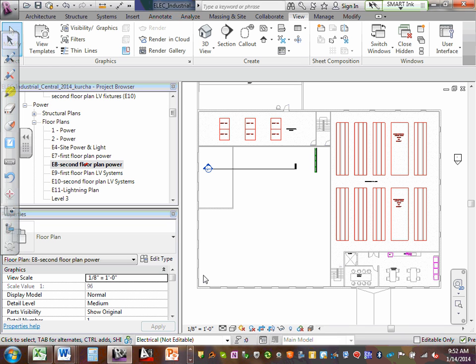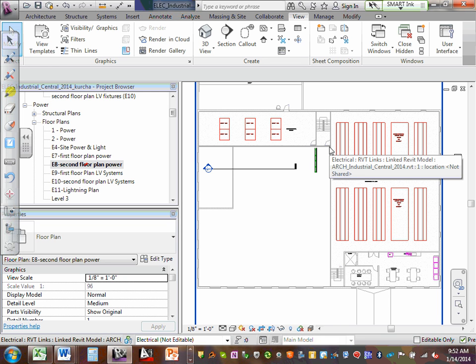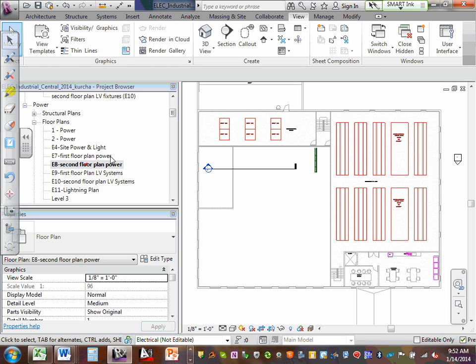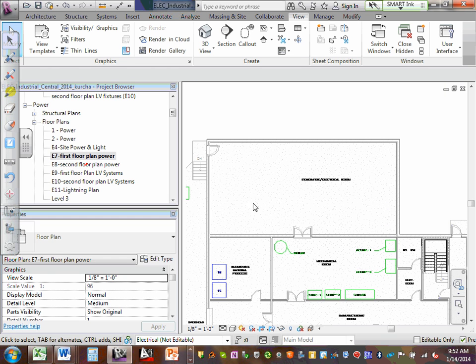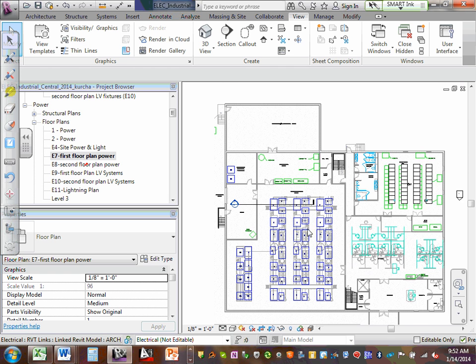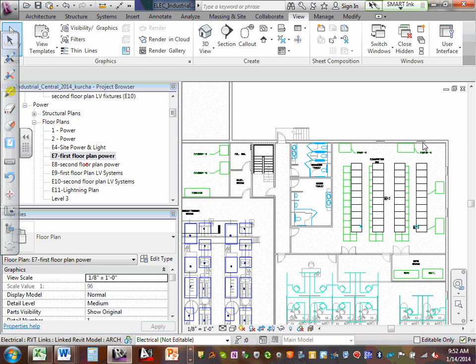We're also asking for fire alarm protection in the manufacturing floor, in addition to what the code says, and we typically did beam smoke detectors. Sure, and that was the first floor, right in here. And then we do have a data center right in here, and we're requiring a pre-action system here, with below floor and above floor smoke detectors, and the criteria.